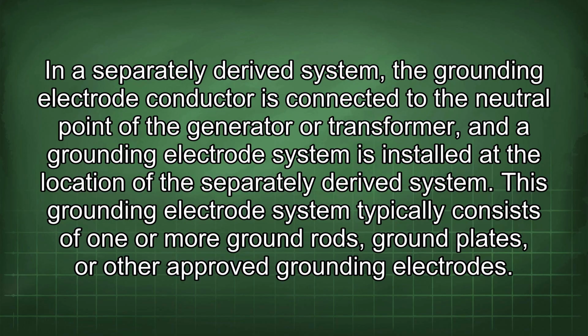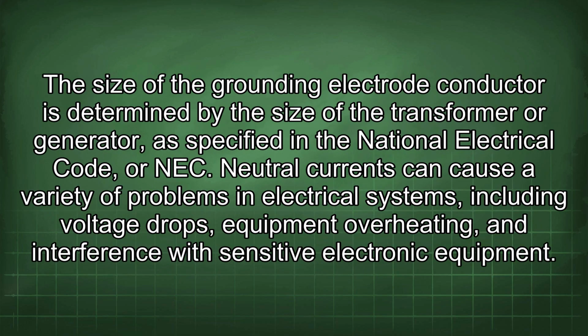This grounding electrode system typically consists of one or more ground rods, ground plates, or other approved grounding electrodes. The size of the grounding electrode conductor is determined by the size of the transformer or generator, as specified in the National Electrical Code, or NEC.